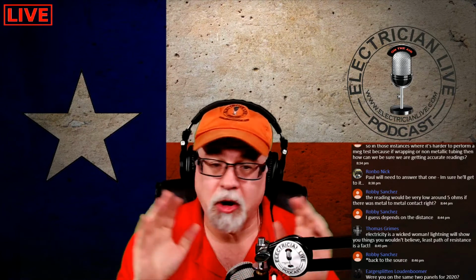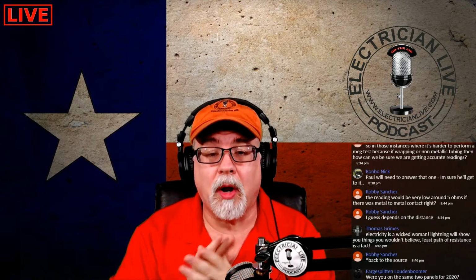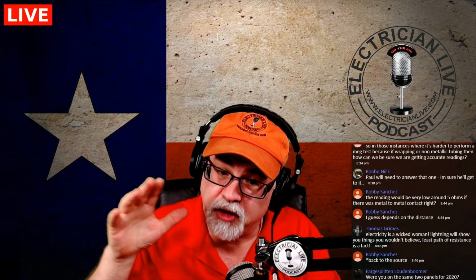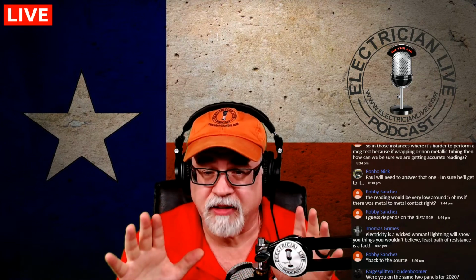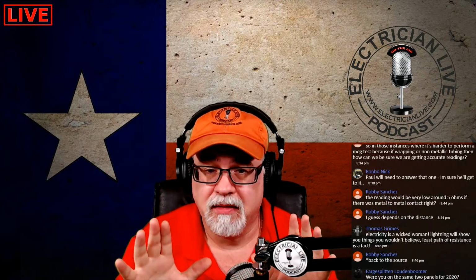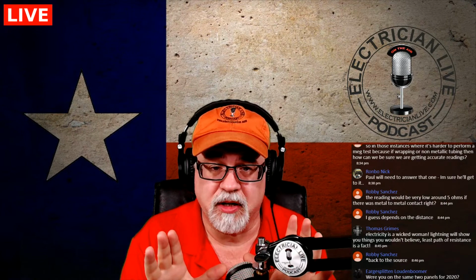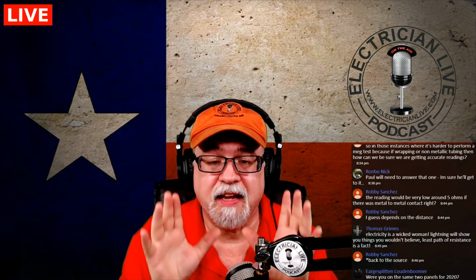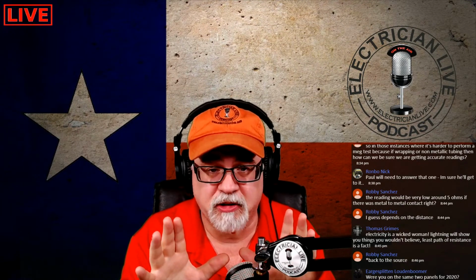Other than that, the MEG readings can go all over the place. It's okay to use the NETA standards as a threshold and make you feel good. And when you get them over 100 megohms, you go, good, let's install this bad boy. All I'm saying is, when you get something that's below 100 and you get it down to maybe 20 megohms, don't freak out yet. Don't start ripping crap out. Reach out to the manufacturer of the wire or cable and give them the story so that they can give you some insight. That's all I'm saying. Okay, just don't start ripping crap out.